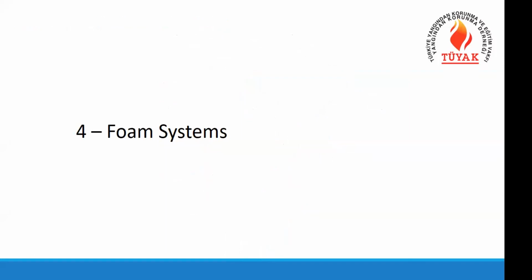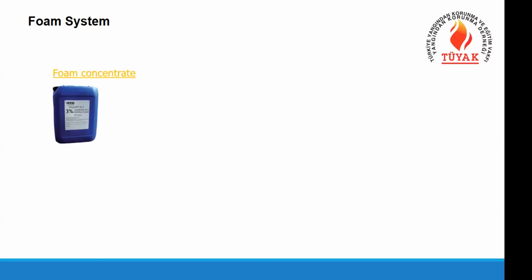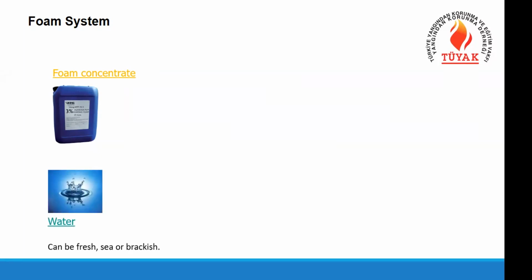So after talking about some water systems like sprinklers, pre-action and deluge systems, let's talk a little bit about foam systems and where they are used. The foam systems consist of different parts, like foam concentrate. The foam concentrate is basically a soap, like a liquid soap. Hand washing soap is a similar material. We combine it with water with some proportioning. For example, for 3% proportioning, 97 liters of water is mixed with 3 liters of foam concentrate.